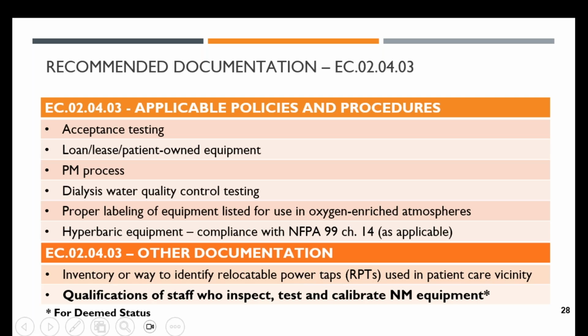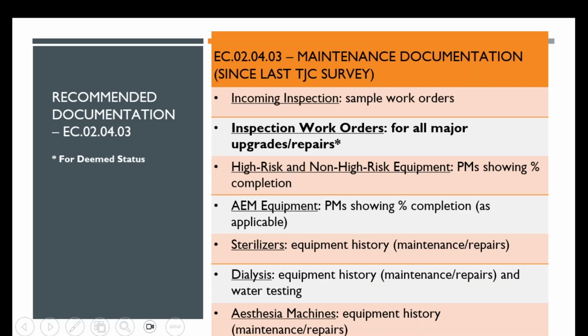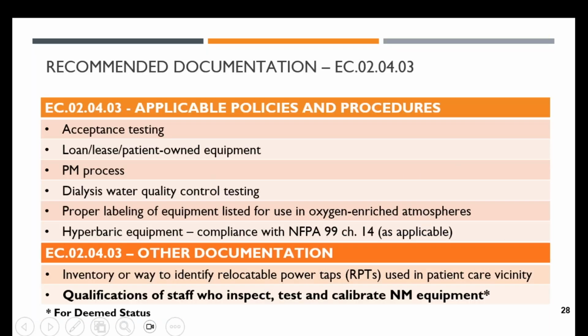And in addition to the policies, you should also have the following documentation: a way to identify your RPTs in the patient care vicinity. We're going to go into the specifics on that. And then for deemed hospitals, as we stated earlier, you should have the qualifications, which includes the certificates of the HTM staff or BMETs that are actually maintaining the equipment on your AEM. Acceptance testing, like incoming inspections, like when you first get equipment into the healthcare facilities, you're looking at it and inspecting it before clinical use.